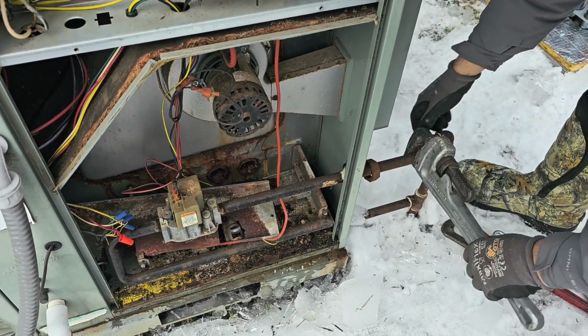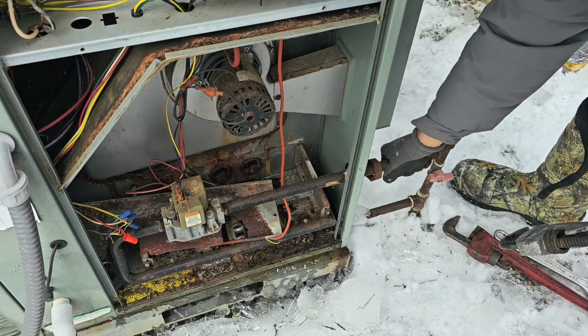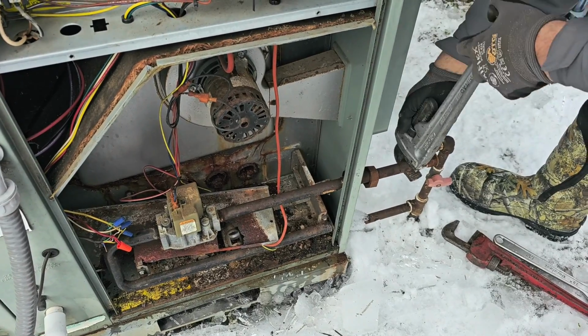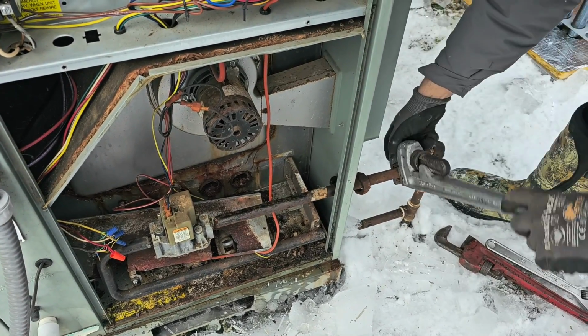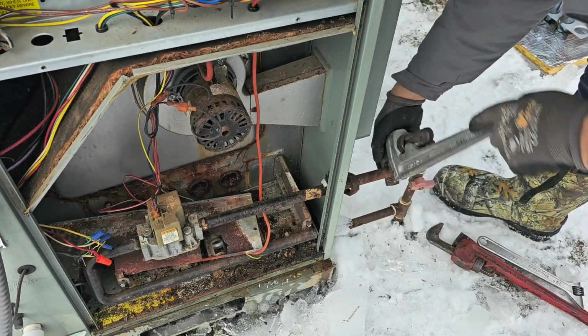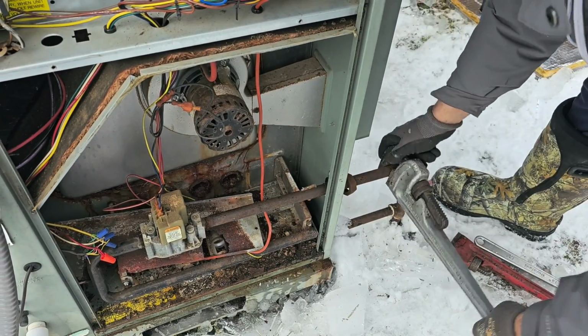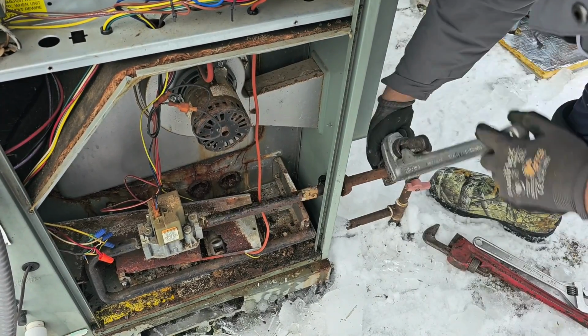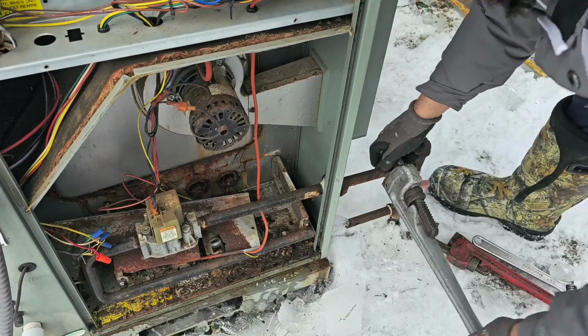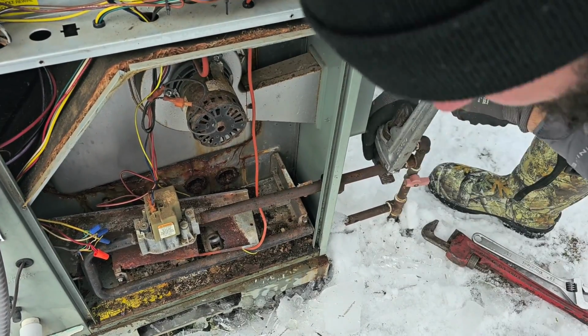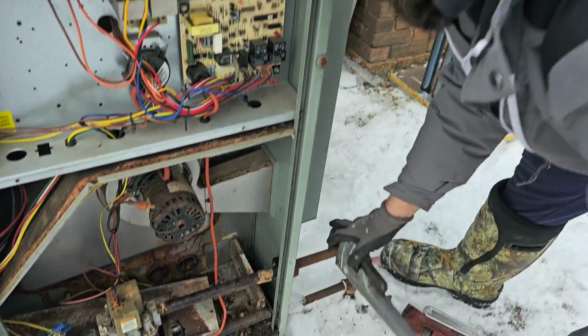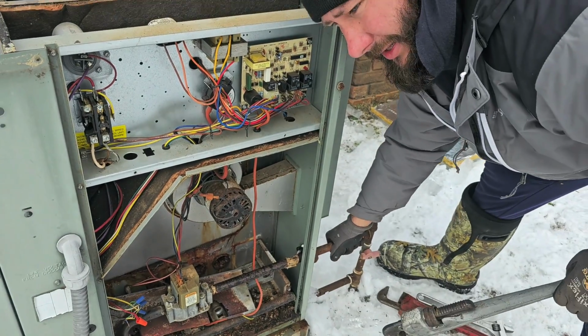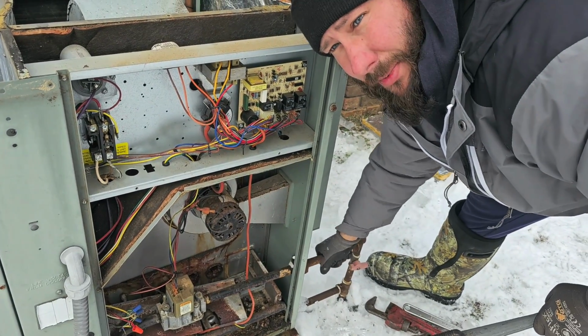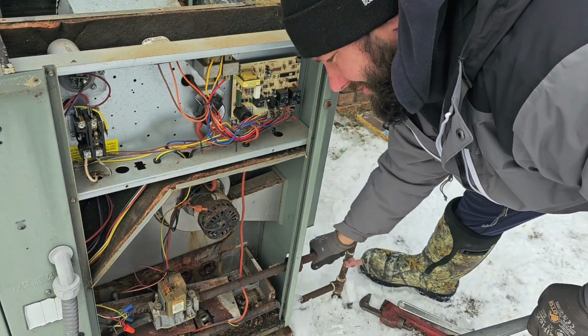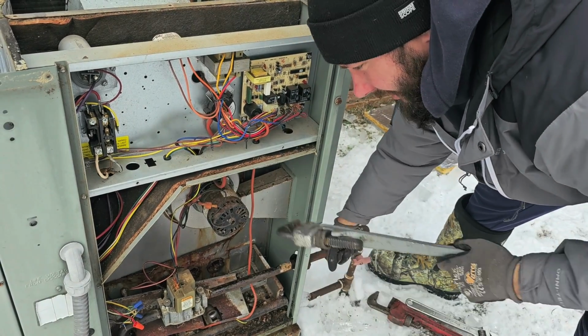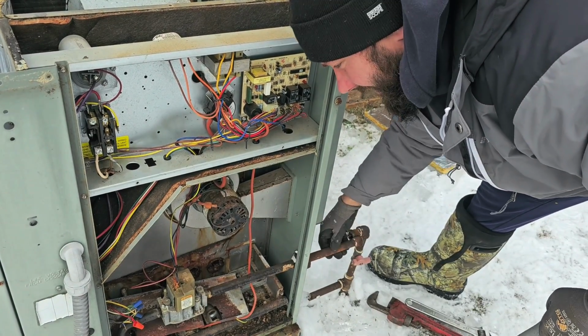Anytime you order a heat exchanger, order the inducer motor, the flue box cover, and the burners if they need to be replaced. Most of the time we do that. On this one, we ordered 3 burners. They only sent us 1 burner. So the other 2 burners are coming in today at lunch. So you're only going to see me replace 1, but know that the other burners are coming in. Also, we did not replace the inducer motor because it's working pretty well.